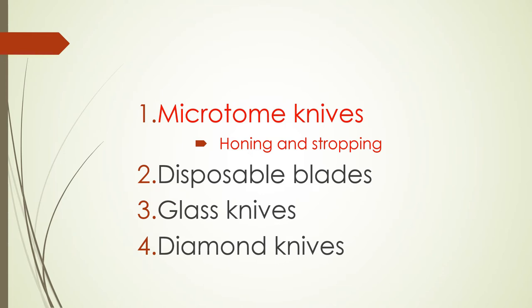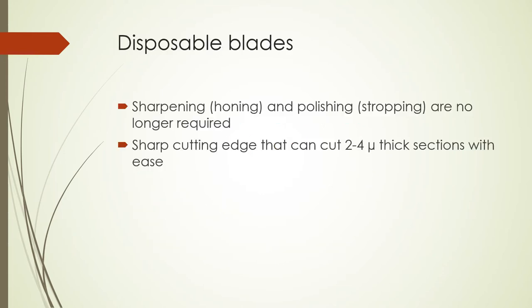Next we have disposable blades, where sharpening and polishing are no longer required — a major relief for medical technologists, since honing and stropping takes a lot of time and effort. Disposable blades can provide 2 to 4 micron thick sections with ease. All we have to do is put the blade onto the knife carrier, and when it's dull, just remove it, throw it out, and replace with a new blade.